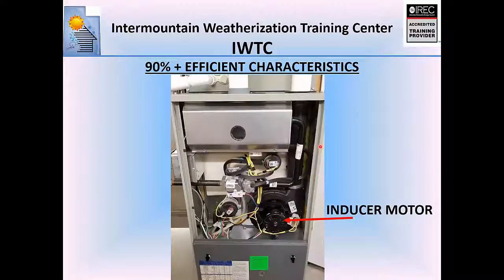Okay. The inducer motors on 90% efficient furnaces do actually force the flue gases out, or pressurize the flue. Remember I talked about on the 80% that once the flue gases get to roughly this point, they rely on natural draft. On 90% efficient furnaces, this guy actually forces the flue gases out. So this pipe is under a positive pressure.